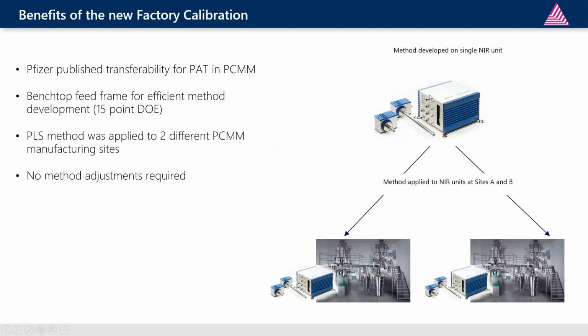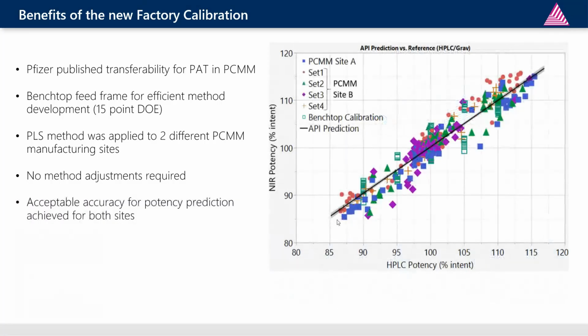This method was built on the single unit with the mini feed frame, with a low amount of material, so very little material was required for that test. The method was then applied to 2 PCMM manufacturing sites with their own NIR systems. There was no method adjustment done during this transfer, and the method was just used as is on the 2 instruments. The validation plot shows a very narrow and very tight calibration, which is an acceptable accuracy for a potency prediction for these 2 sites. The actual concentration of saccharine was around 20% for this trial.